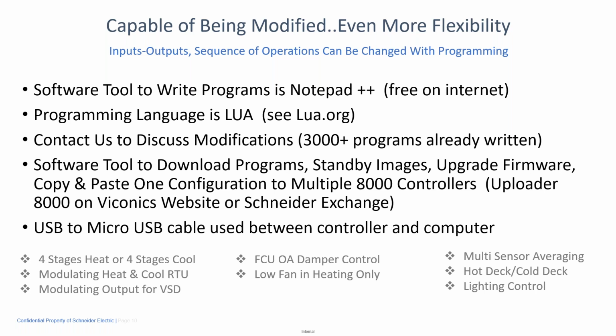program's already done. Maybe you got fan coil units that are more like unit ventilators, and you need outdoor damper control. That's already done. Oh, guess what? Maybe somebody only wants low fan and heating in heating mode for a fan coil unit. That can be done, right?